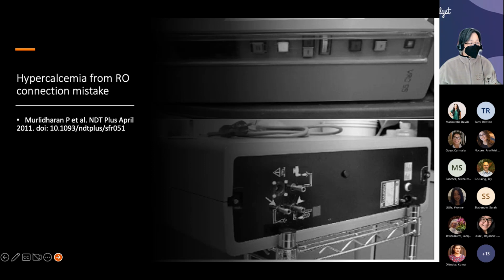The patient misconnected the RO system to the machine, so the water going to the machine and thus the patient was not the product water, not the purified RO water, but the effluent wastewater. That wastewater had a massively high calcium concentration, and the patient became ill within about 30 to 45 minutes. By the time they reached the hospital, their calcium level was almost 20. It was a simple error of connecting to the wrong outlet on the RO machine.